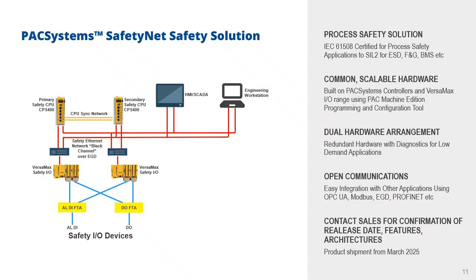Now, we've gone through various processes to get this approved. We're currently working with a dual hardware arrangement. This redundant hardware allows us to have the diagnostics to be used for low demand applications and to meet the requirements for SIL2. Other benefits we have is open communications for easy integration with other applications. So our primary protocol will be OPC UA, but we also support Modbus, we support Ethernet Global Data, and potentially we can support integration with other systems using Profinet and our other standard networks.